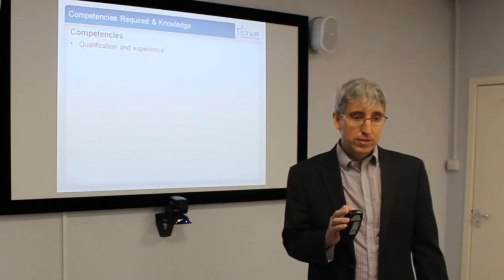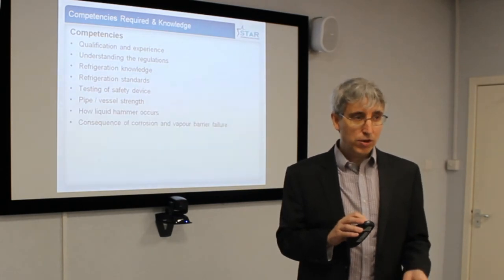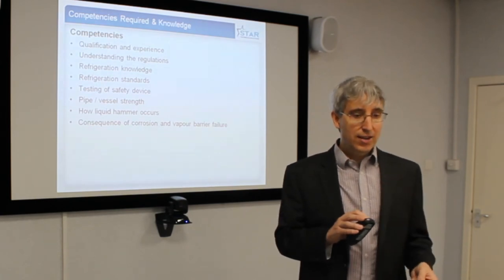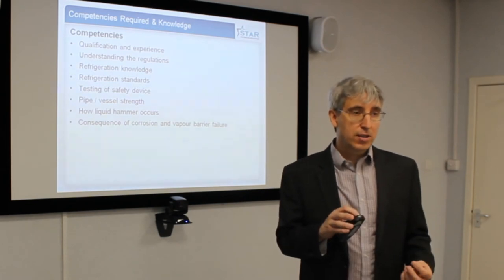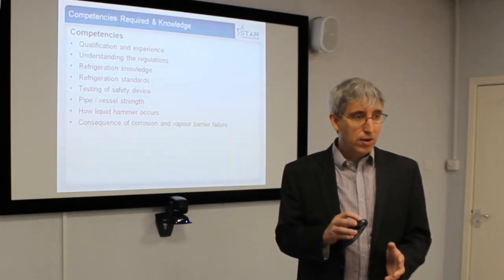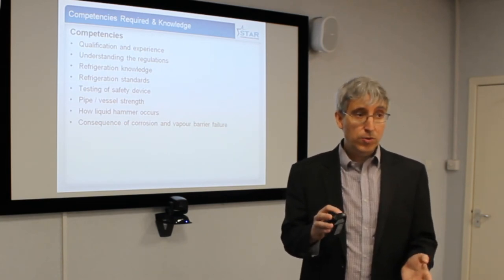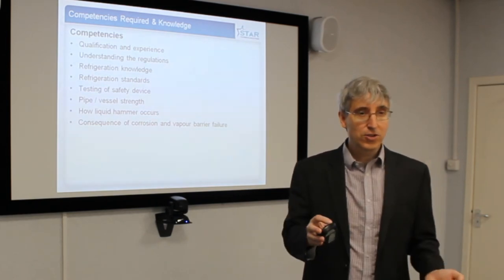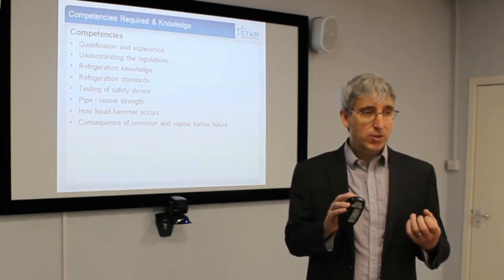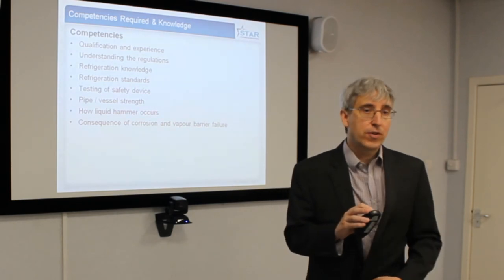What are the competencies required? Qualification and experience, and understanding the regulation. But the reality is that it comes down to having a good, solid refrigeration background — understanding the regulations, understanding things like liquid hammer, and understanding how the system actually works. If you're coming from a non-refrigeration background and do not understand the risks, you're going to be at a weak point. If you're a day-to-day person looking at a boiler, you'll assume there's internal pipe corrosion — but modern refrigeration systems don't have that. So you look at the wrong things and request the wrong type of inspections — you'll waste money, and your risk-based inspection mechanism will be all wrong. Having sound refrigeration knowledge is the most important factor.